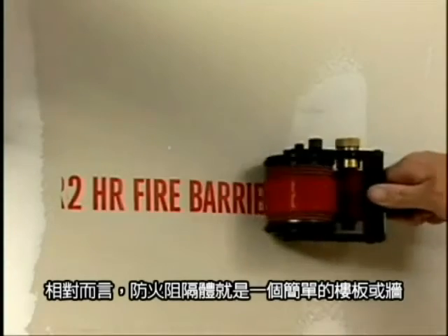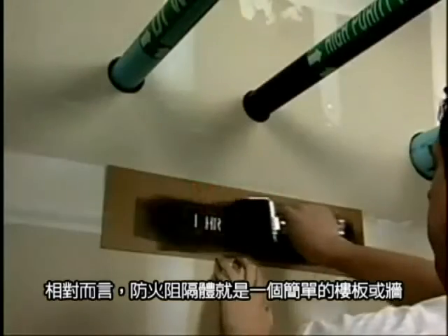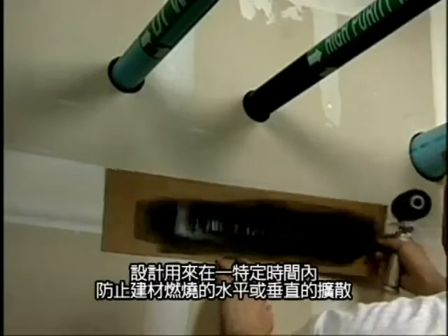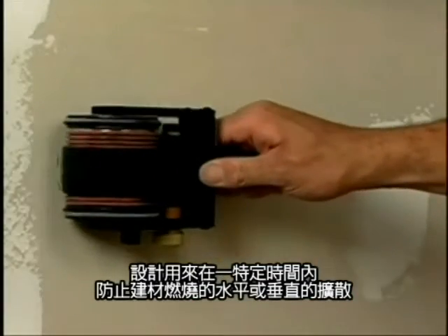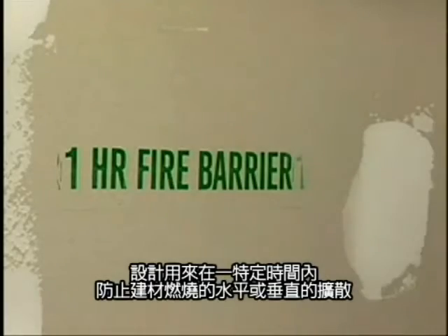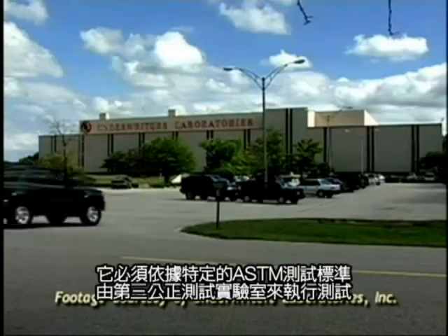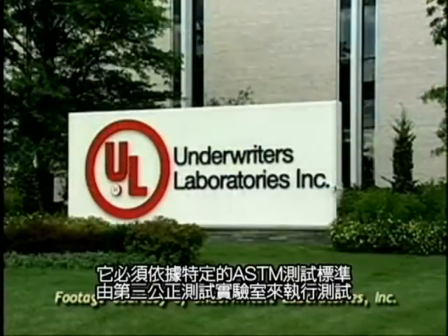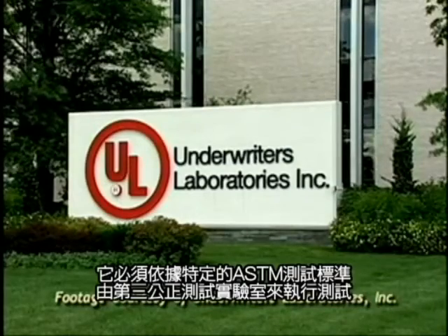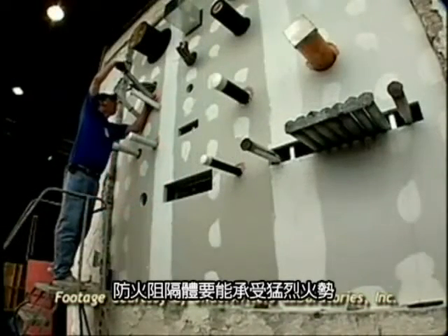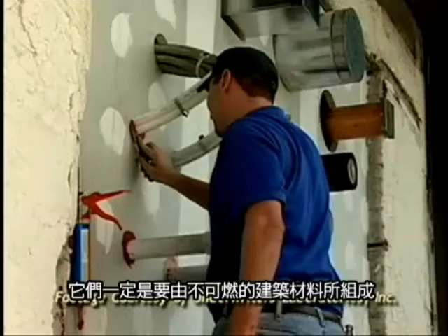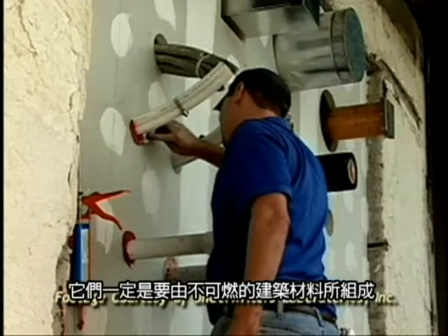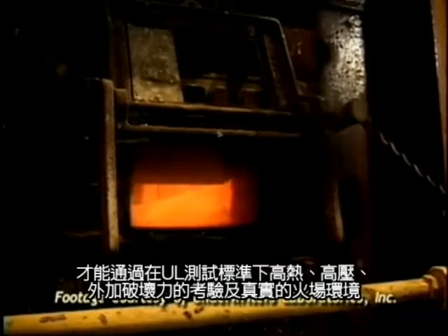A fire barrier, by contrast, is simply a wall or floor designed to prevent the products of combustion from spreading vertically or horizontally for a specific amount of time, and is tested by a third-party lab to specific ASTM test standards. For these fire barriers to withstand such forces, they must be constructed from non-combustible building materials that are strong enough to survive the enormous heat, pressure, and destructive forces of both the UL test standards as well as real fires.